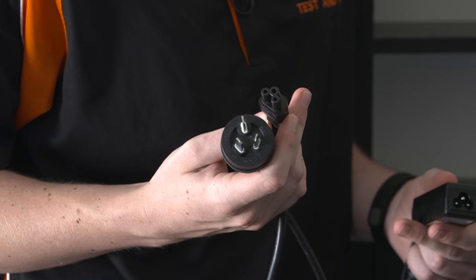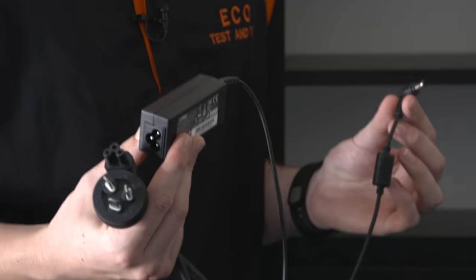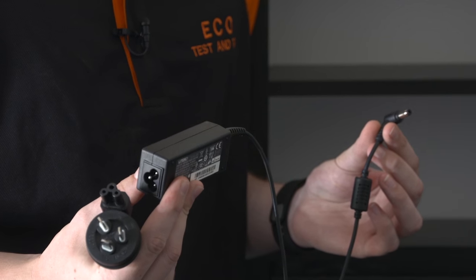As with most laptop chargers, this laptop charger will be tested in two parts. The first component will be the IEC lead. This particular one is a clover leaf. The second part is the power adapter. Both items need to be tested and tagged separately.